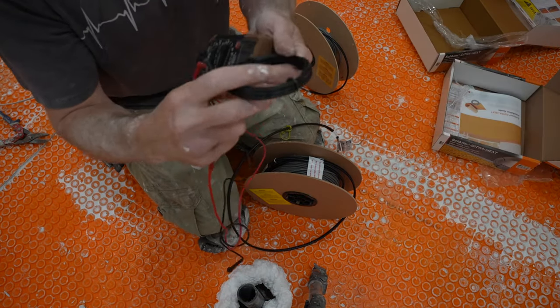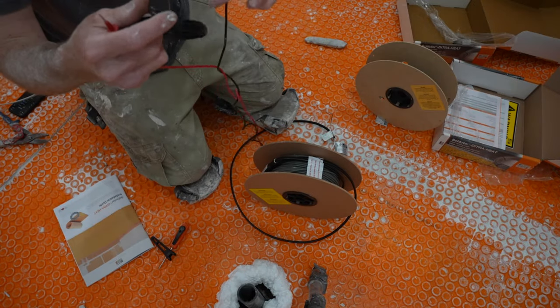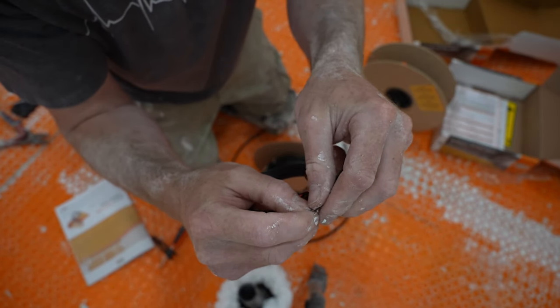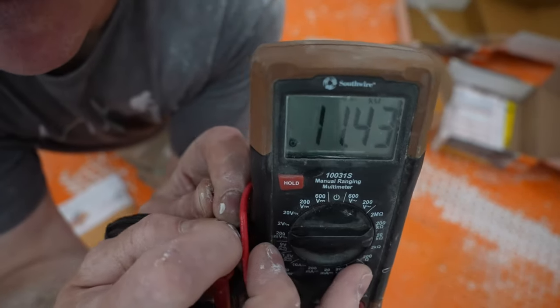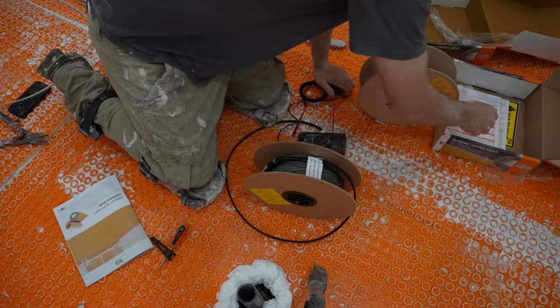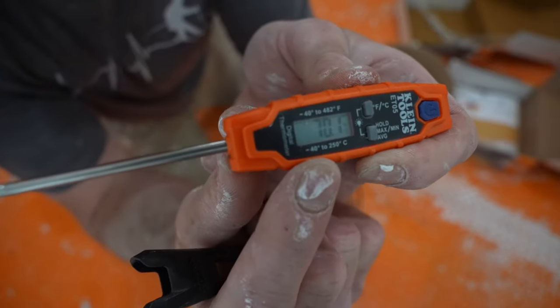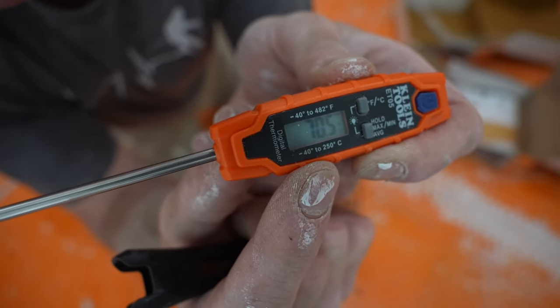The third test: set your meter to the 20K setting, then take your sensor wires and connect the two leads on your sensor. We're reading 11.43. This is essentially a temperature reader — you want to find out what the temperature is in your room. Right now we're at 70.2 degrees, so note that reading.